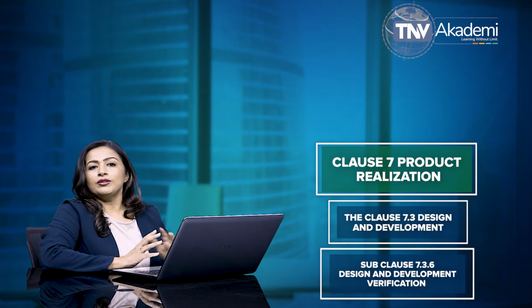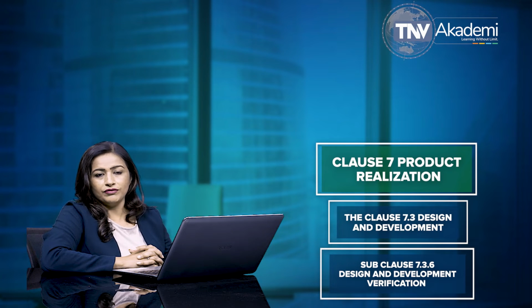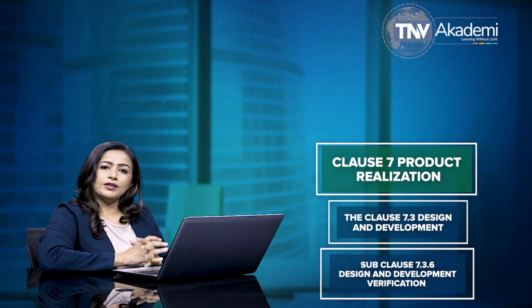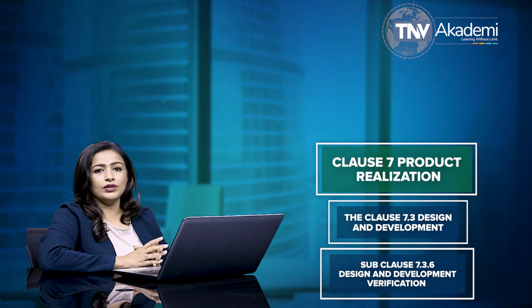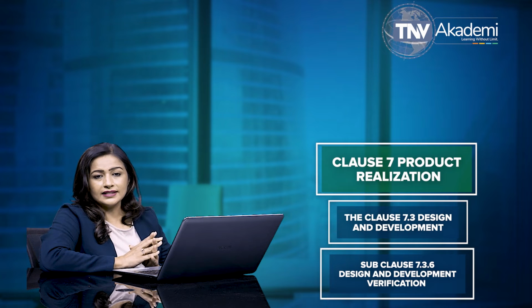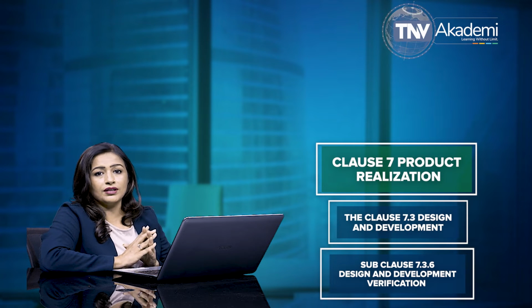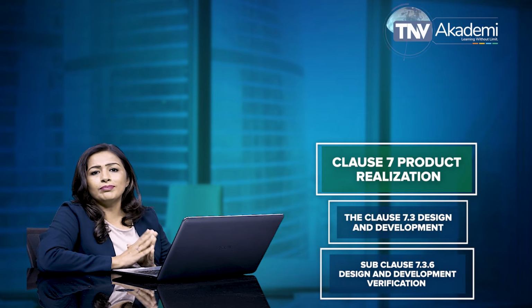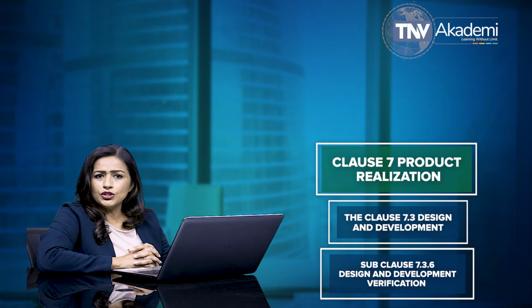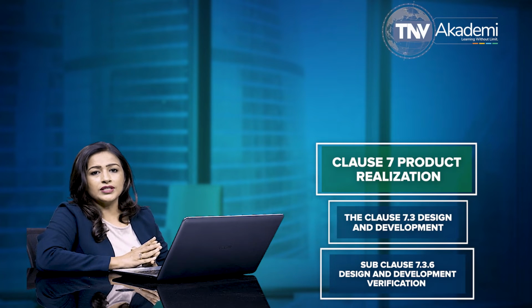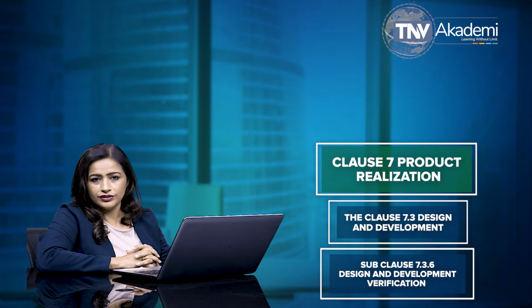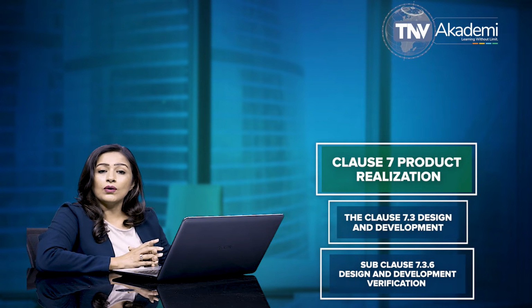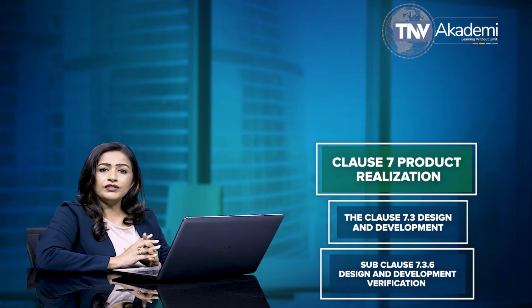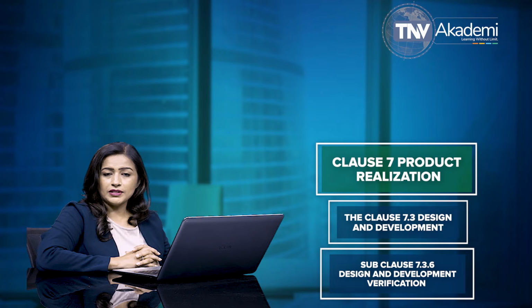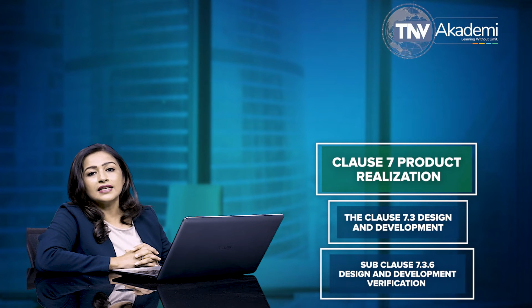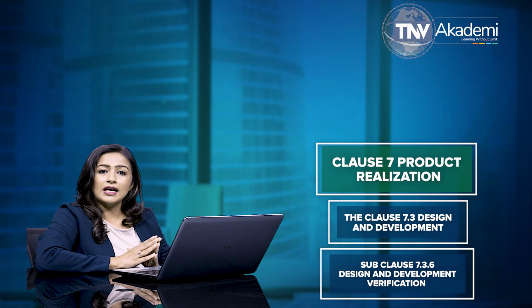Now coming to subclause 7.3.6, Design and Development Verification. This subclause 7.3.6 of ISO 13485:2016 states that design and development verification is required to be performed in accordance with planned and documented arrangements to ensure that the design and development outputs have met the design and development input requirements. As per this subclause, the organization is required to document verification plans including methods, acceptance criteria, and, as appropriate, statistical techniques with rationale for sample size.